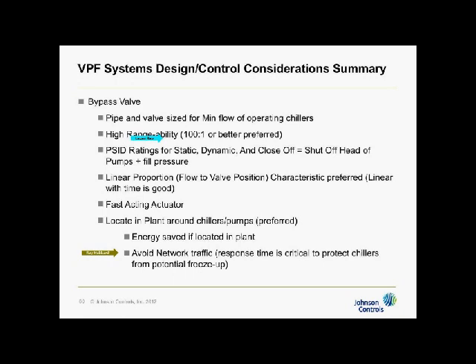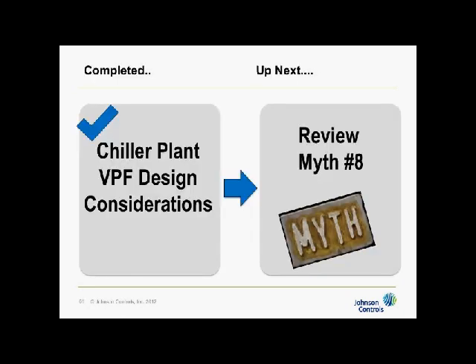Because if I put it all the way out at the end of the system, the bypass flow in bypass mode has to travel through the entire system all the way to the end and come back. And that's just wasting pump energy during bypass operation. So locating it in the plant saves energy, and it also makes it easy. So those are the design considerations for VPF on the chill water side.